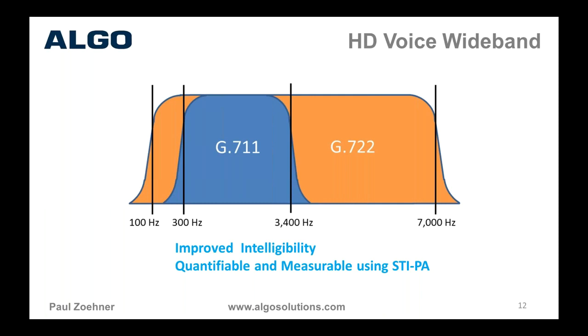That lower band doesn't contribute to intelligibility. It does give the voice a more natural sound. For music, you would probably want that. But for high intelligibility paging, many of the speakers will actually cut off that low end and focus on the high end because we don't want to overpower an environment, especially if it's a reverberant environment. But we do want to get that high intelligibility from that 4 kilohertz octave.